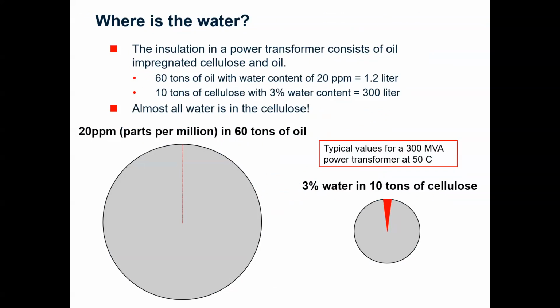So where do we have water? The insulation of a power transformer is based mainly on pressboard, paper, and oil. We have a lot of oil, like 60 tons on average in a large transformer, but oil has very low moisture content. When it is dry, it is like 20 ppm, for example, which is very little compared to the amount of oil. Whereas in cellulose, we can have quite a large amount of water inside. So the conclusion is that almost all water is inside the paper or cellulose.